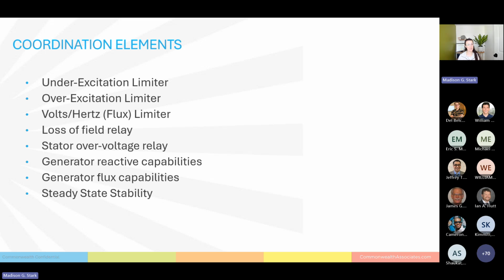And then the capabilities that we're looking to coordinate, we have the generator reactive capabilities, which is really the power output capabilities of the generator, which is your thermal limitations. How much power can it physically produce? And then you have your generator flux capabilities, which relate to the core of the generator. How much current, how much magnetic field can this generator handle? And then you have the steady state stability of the generator, which is how far can you push that rotor angle before it loses synchronization with the grid.